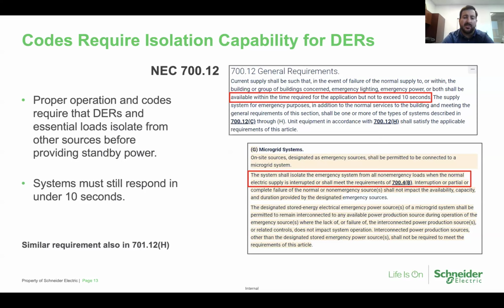But the National Electric Code goes further and states that, and I'll start at the bottom here, the system shall isolate the emergency system from all non-emergency loads when normal electric supply is interrupted and shall meet the requirements, blah, blah, blah. Well, let's summarize that. It's basically saying that if you have, say, a battery energy storage system that you're using in parallel with utility, but you want to use it for emergency standby power, when you have that outage, you want to kick it on as a standby source, it's got to be isolated from that utility, so it can't backfeed the utility or overload, as well as it has to be isolated together with those critical loads.